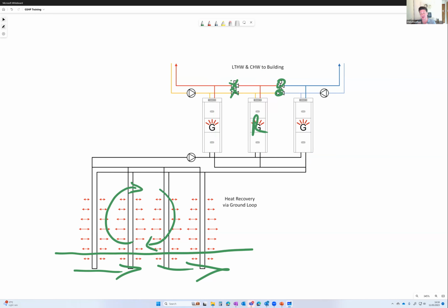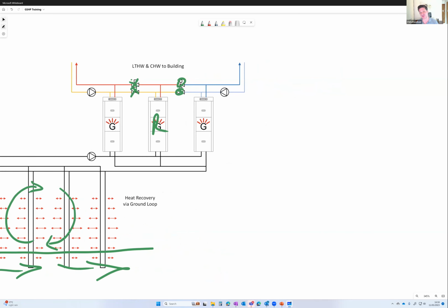There's a few considerations in terms of not just how many heat pumps you have, but what size each heat pump is. And a common mistake that's made with this type of system is, let's say, for example, we've got a commercial building with a little, say, 10 kilowatt server room load on there. Let's say this heat pump's 100 kilowatts and 100 kilowatts. And let's say we're in winter, we are heating only, but that 10 kilowatt server room load's still going. So we'd have to turn off that 100 kilowatt heat pump, reverse it, and turn on a 100 kilowatt heat pump just to service that little 10 kilowatt load.